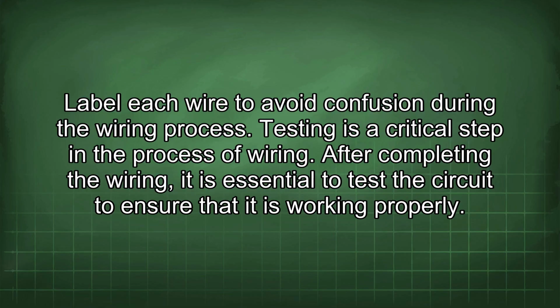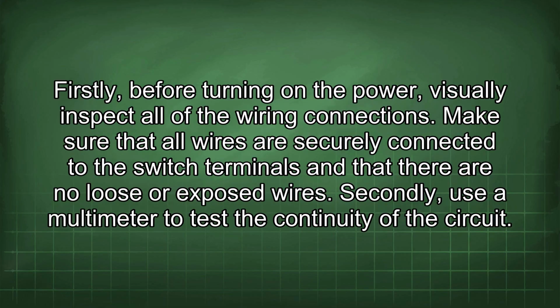Testing is a critical step in the process of wiring. After completing the wiring, it is essential to test the circuit to ensure that it is working properly. Firstly, before turning on the power, visually inspect all of the wiring connections. Make sure that all wires are securely connected to the switch terminals and that there are no loose or exposed wires. Secondly, use a multimeter to test the continuity of the circuit.